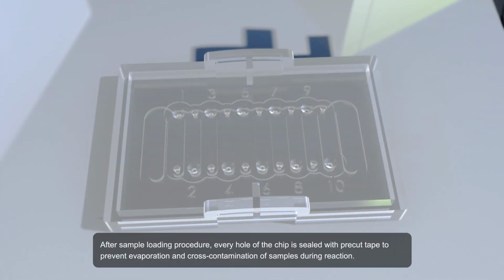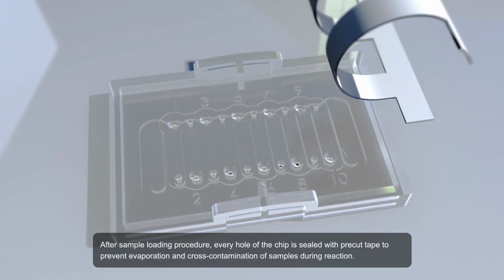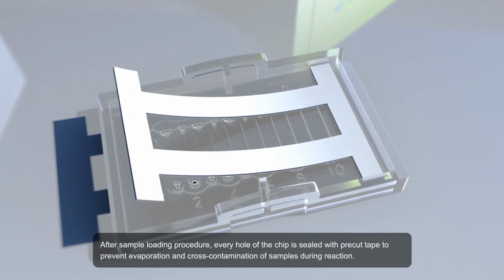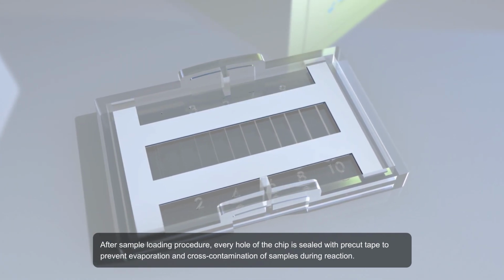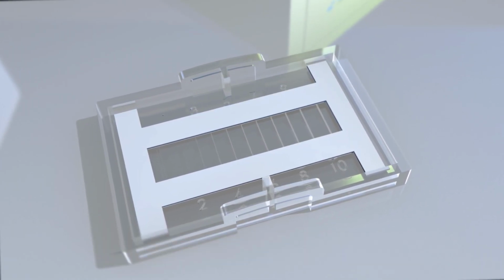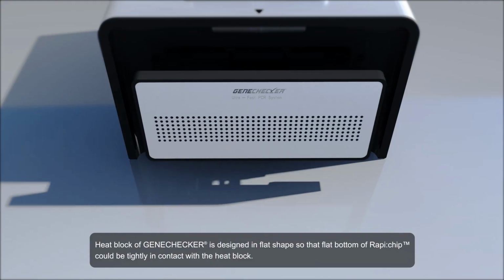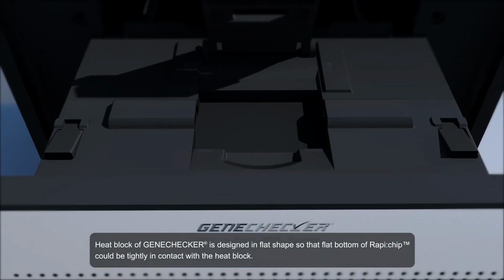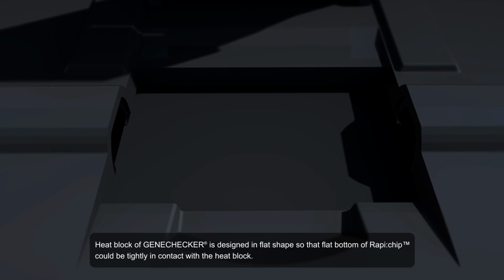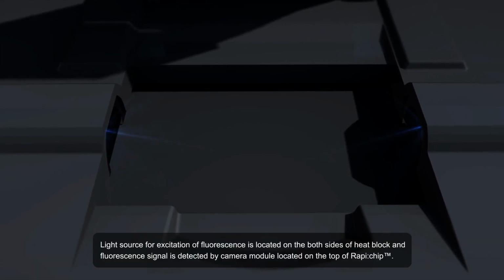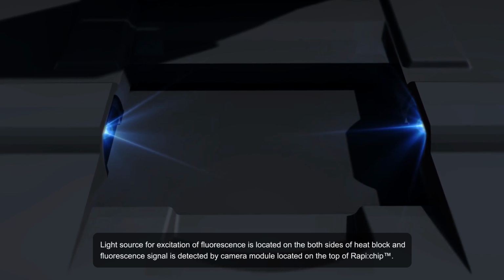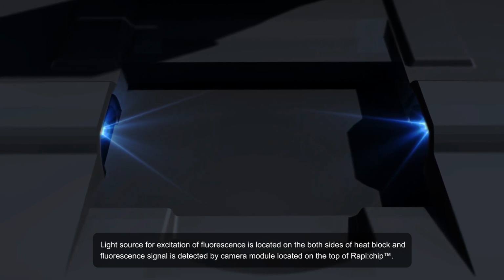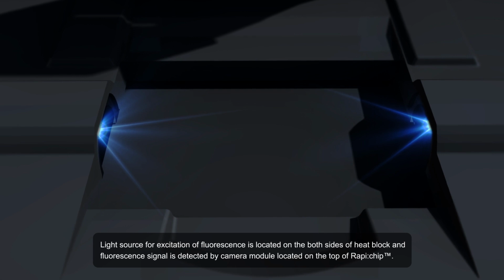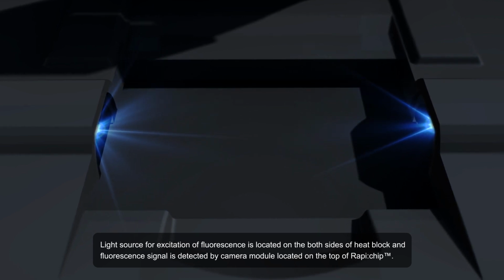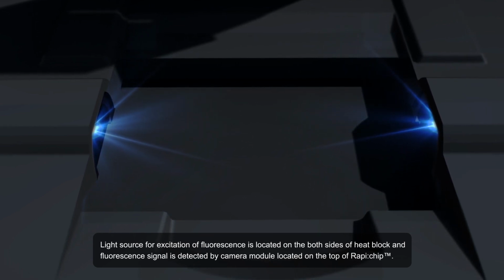After sample loading procedure, every hole in the chip is sealed with pre-cut tape to prevent evaporation and cross-contamination of samples during reaction. Heat block of GENECHECKER is designed in flat shape so that flat bottom of RapiChip could be tightly in contact with the heat block. Light source for excitation of fluorescence is located on both sides of the heat block, and fluorescence signal is detected by camera module located on the top of RapiChip.